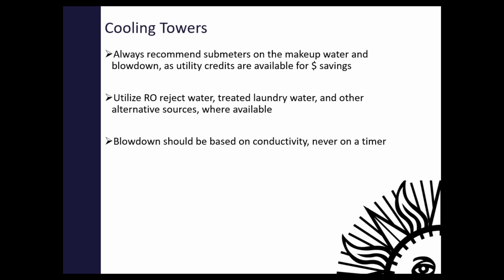There are sites that have continuous blowdown, meaning they always bleed off, like 3 GPM from the tower, no matter what, at all hours. That's terrible. That's a terrible practice, because your cycles of concentration could range from 2 up to 10, just depending on how often that cooling tower is used.